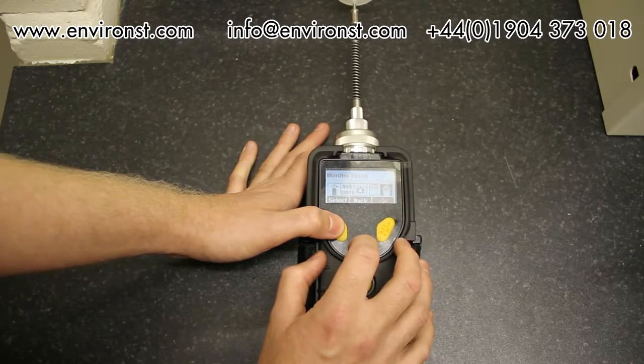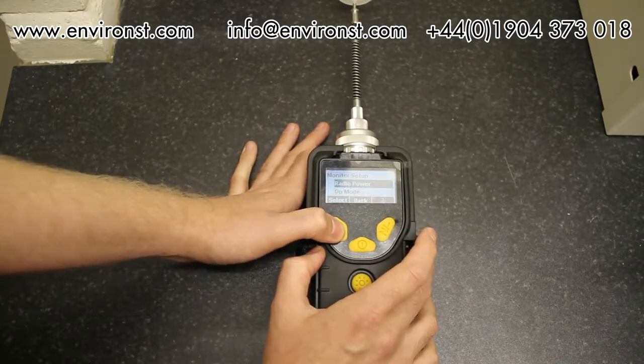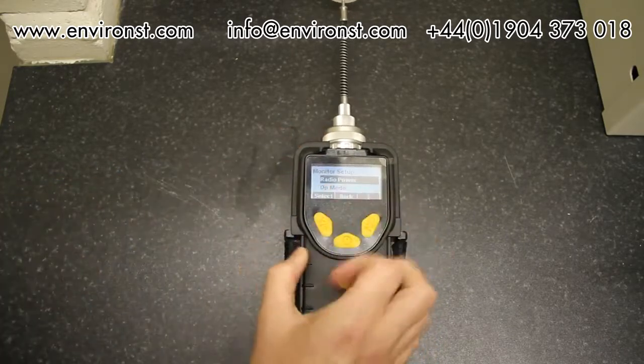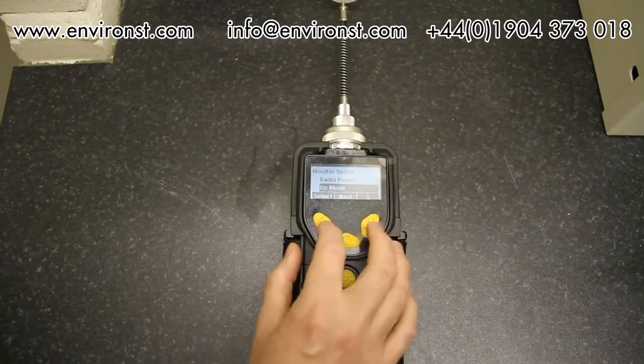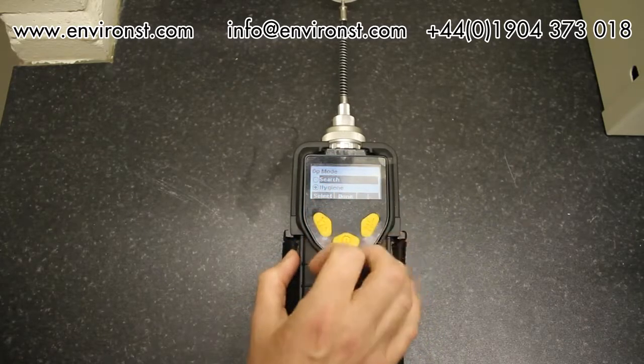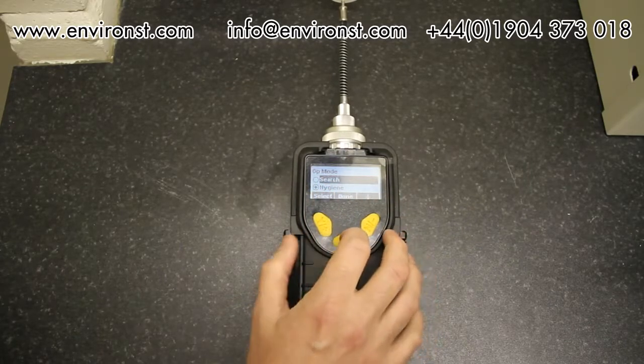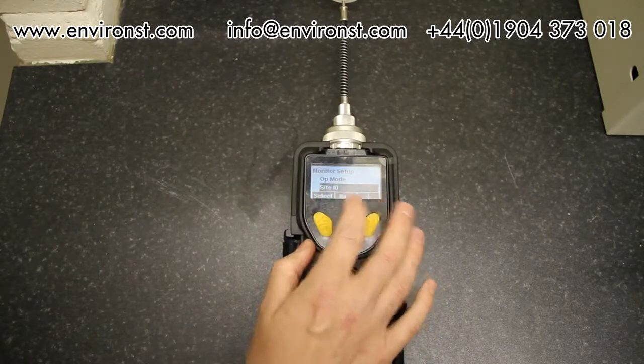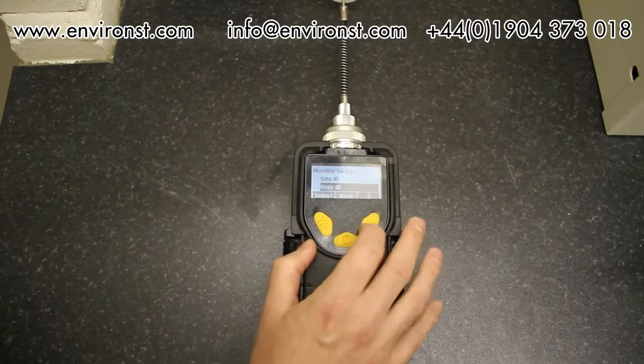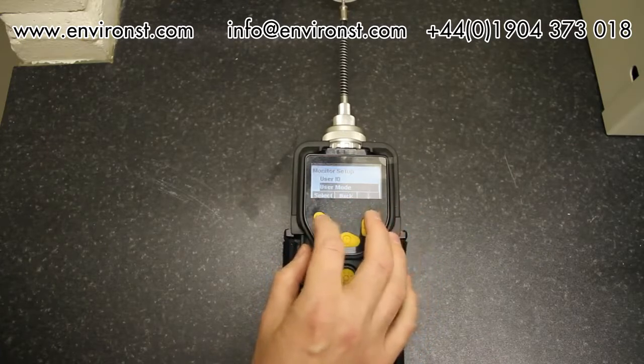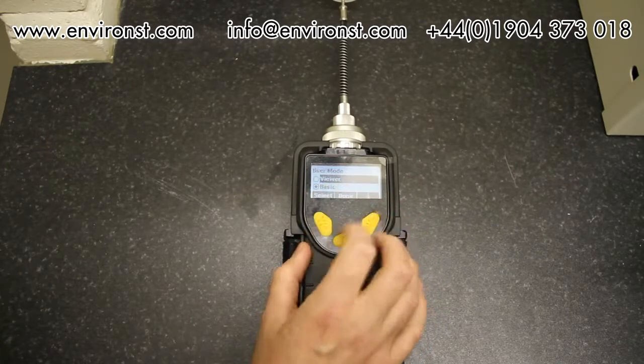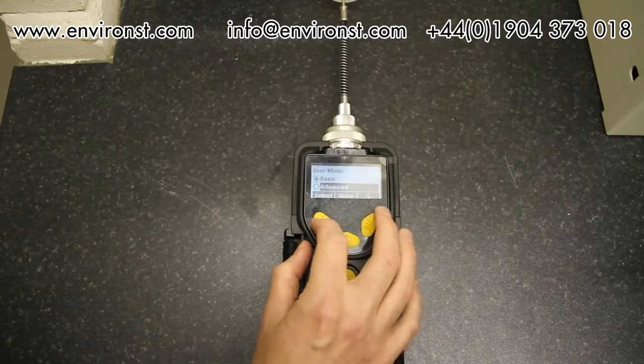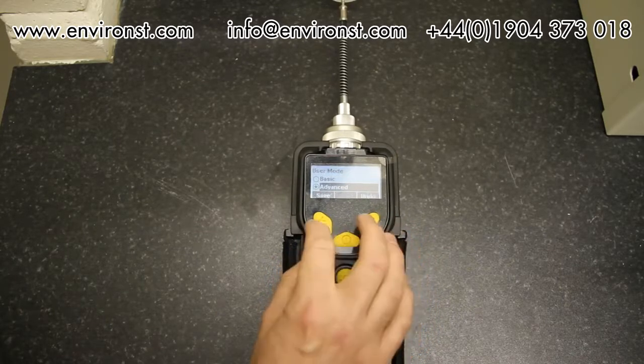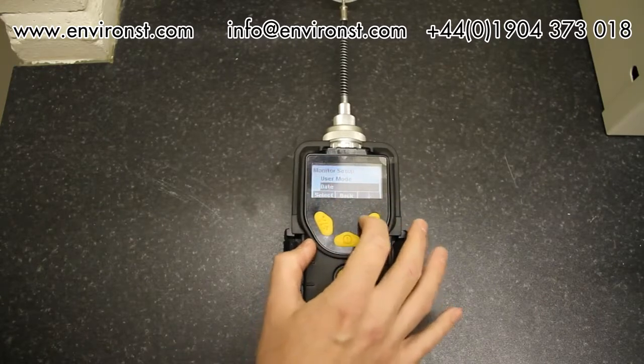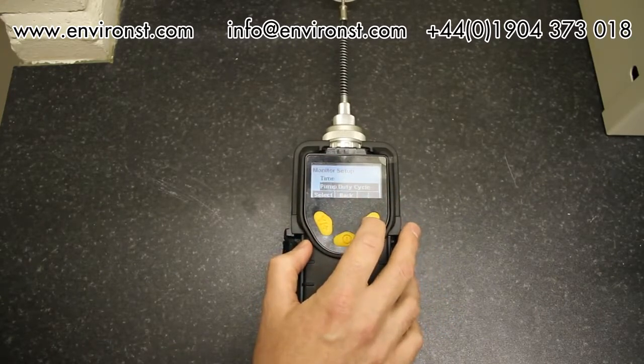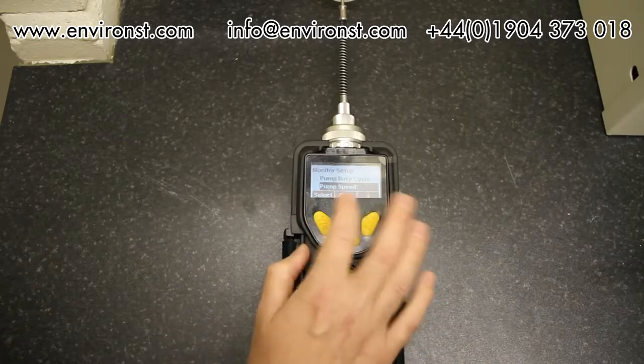And that's it for data logging. Now if we scroll across to the monitor setup, now this is where I can turn radio power on and off, change the operation mode. So if I select this, I can go into search mode or hygiene mode, enter a site ID, a user ID, enter a user mode. So if I go into this, you can have viewer, basic or advanced. I'm going to put it into advanced now, save that, change the date, change the time, change the pump duty cycle, change the pump speed.